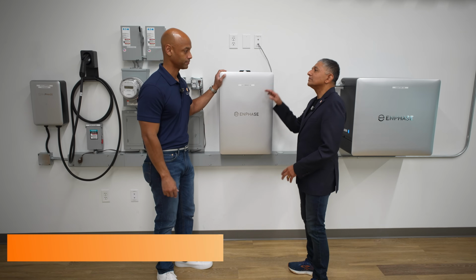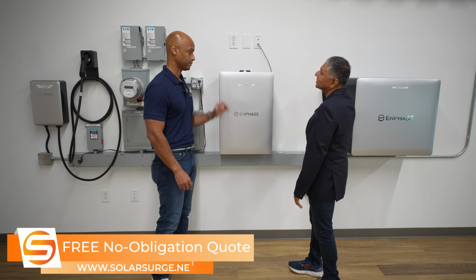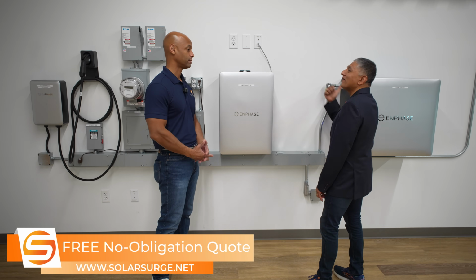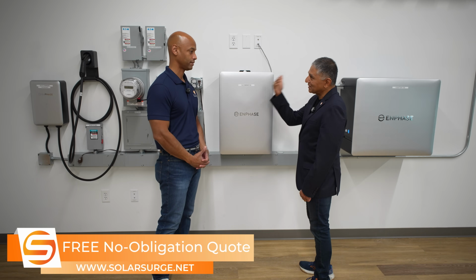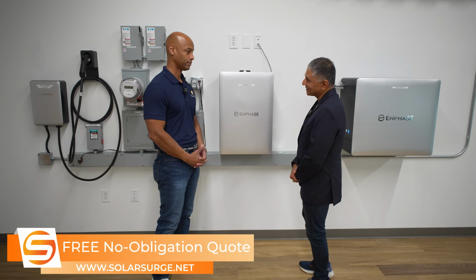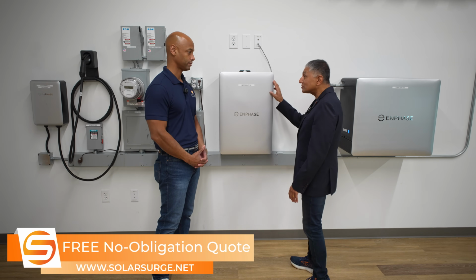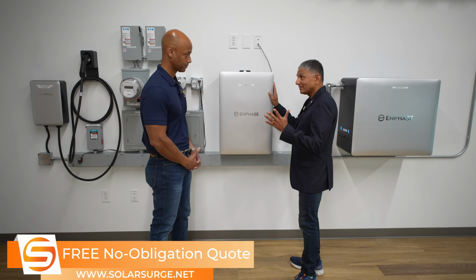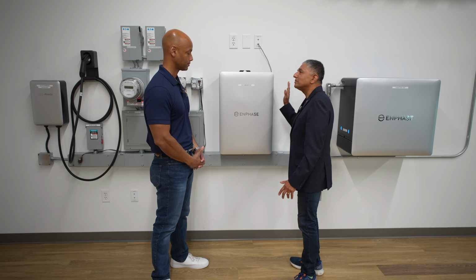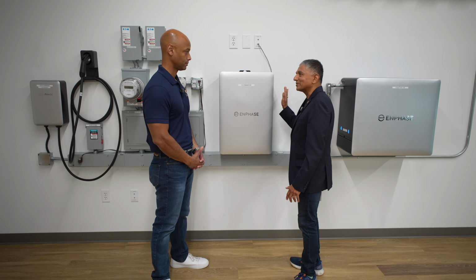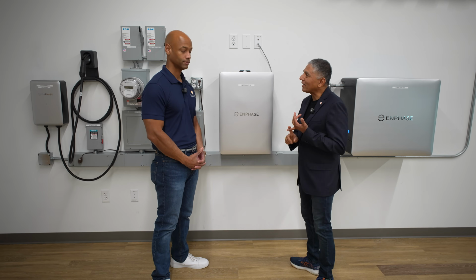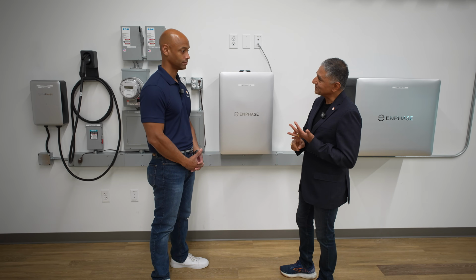Precisely. And so you're not limited to the 20 amp breaker on a 100 amp panel to comply with the 120% rule. Correct. So that doesn't apply anymore. So in theory, there should never be a need to do main panel upgrades anymore. So CTs are gone, main panel upgrades are gone, right?